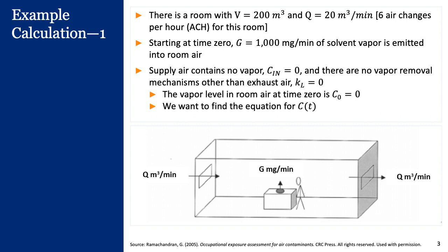And so in 1 hour, there's 1,200 cubic meters of air moving through it. It means that the air in this room has been completely changed over 6 times, because the airflow is 1,200 divided by 200 cubic meters. So we are left with 6 air changes per hour.